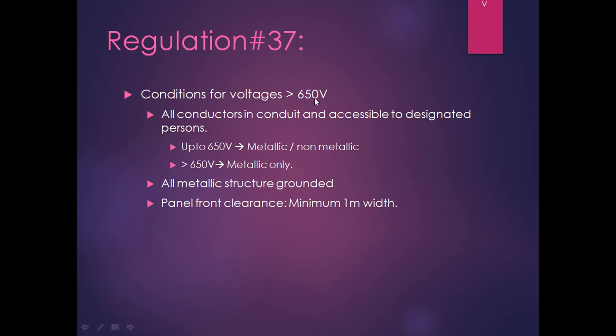For conditions of voltages more than 650 volt, all conductors in conduit and accessible to designated persons only. Whatever conductor you are laying, they should be laid within the conduit only. Up to 650 volt, you can use the metallic conduit as well as non-metallic conduit. These non-metallic conduits actually are preferred for the sea kind of environment or where the environmental condition is very harsh, because metal has a tendency towards corrosion. There non-metallic conduit is preferred. However, if the voltage level is more than 650 volt, only metallic conduit shall be used. All the metallic structure shall be grounded. Metallic structure means the base frame of a motor and pumps, the body of the motors, etc. Panel front clearances shall be at least 1 meter in width.